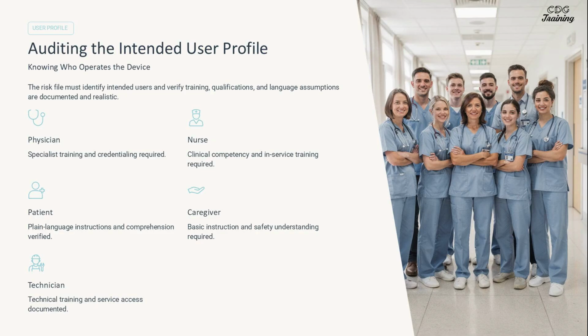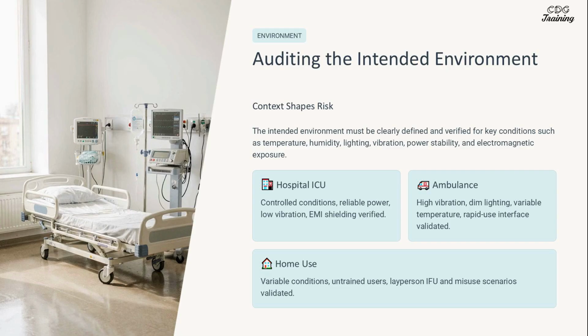The risk file must identify intended users and verify their training, qualifications, and language assumptions, ensuring they are documented and realistic. The intended environment must be clearly defined and verified for key conditions like temperature, humidity, and lighting, ensuring safe device operation.